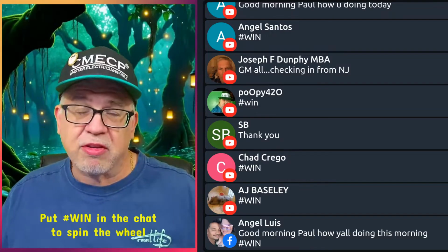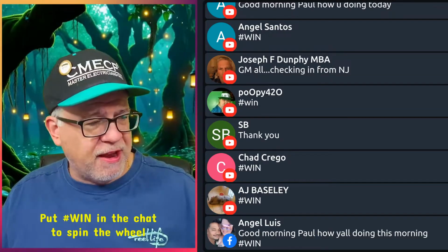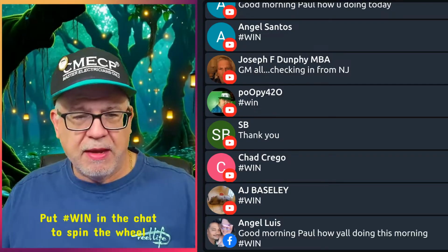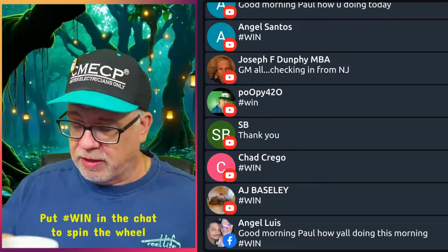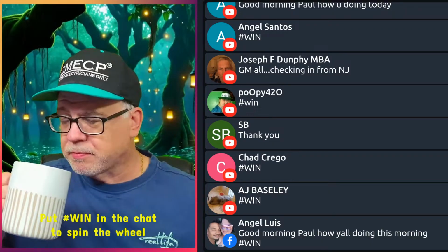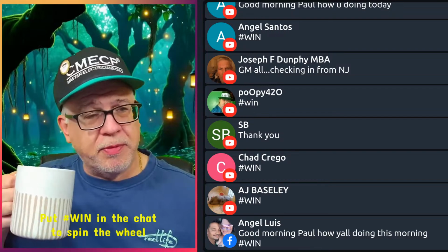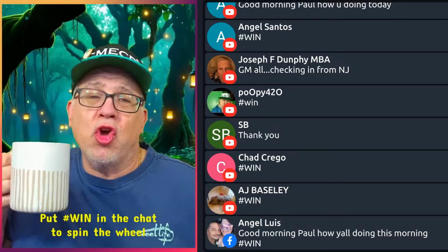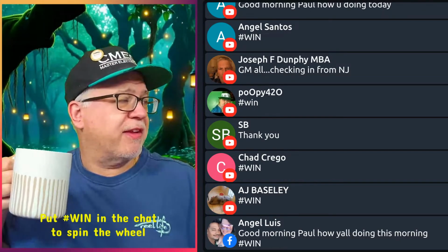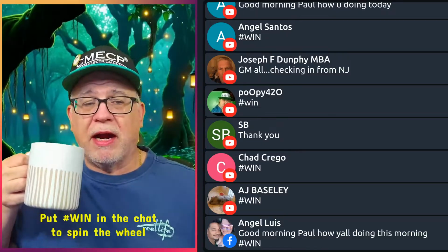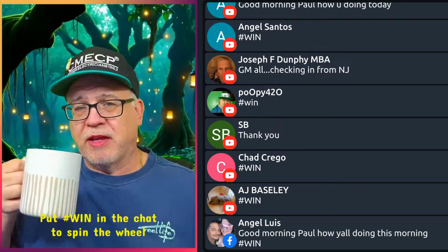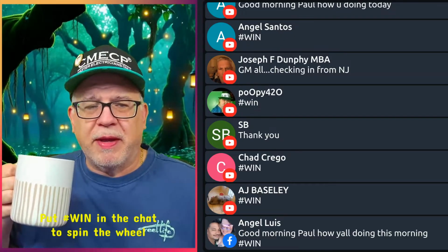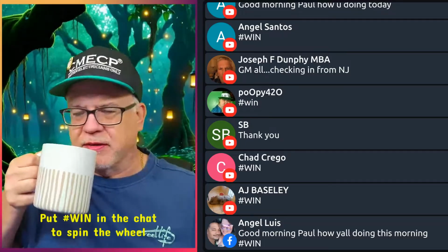Again, you can reach out to the manufacturers. Don't be afraid. I get calls every day with people asking questions about wire and cable, MC cable applications. And we still have people on social media putting videos out and challenging people about using anti-short bushings in MC cable. I mean, you do you, boo. That's what I always have to say to people. You do you. Are they required for MC? They are not, if you use a listed fitting, which you're required to use anyway, 330.6. But it makes people feel better to see that bushing in there.